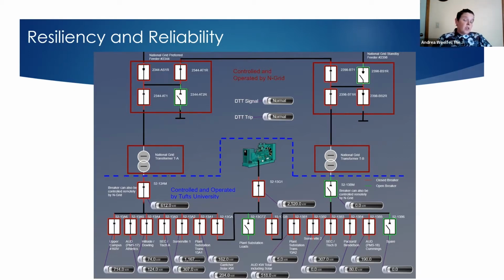This is a graphic that shows our electrical distribution. Prior to this upgrade, the electrical distribution was an aging infrastructure here. So part of the cogen, part of putting in the CEP, was upgrading some of the electric utilities. Right now, all of the breakers you see below the dashed blue line, that's where all the power is inside the CEP. We're either taking it in from the utility or generating ourselves, but we're distributing it through some very sophisticated automated computer controls.